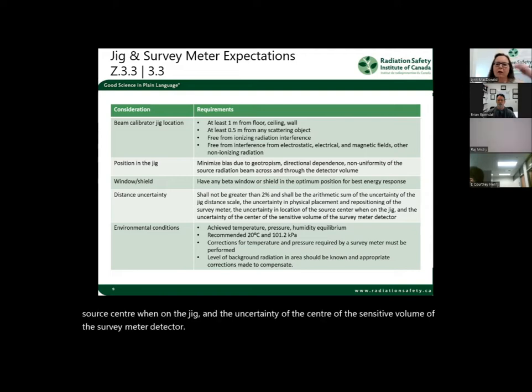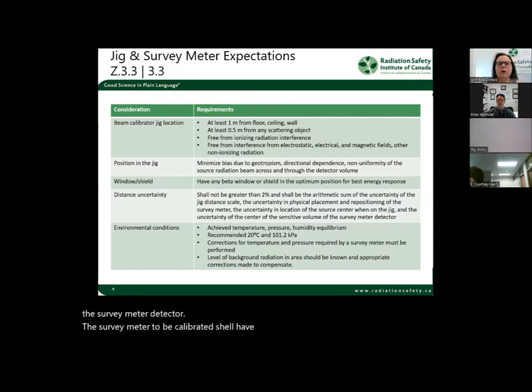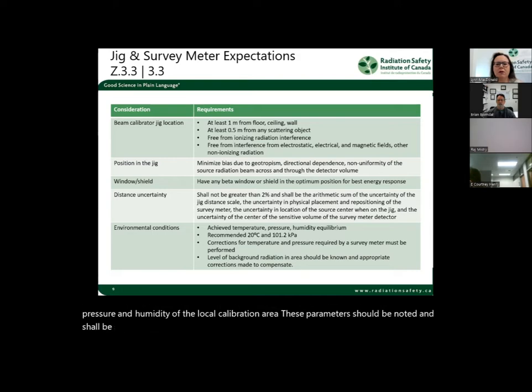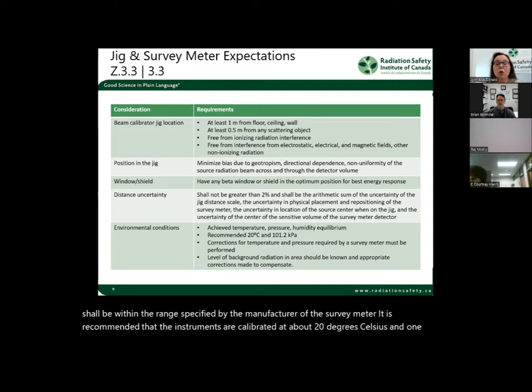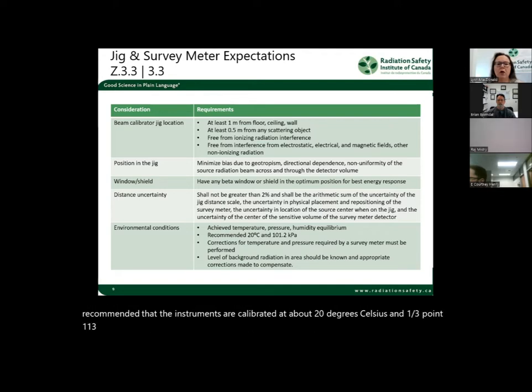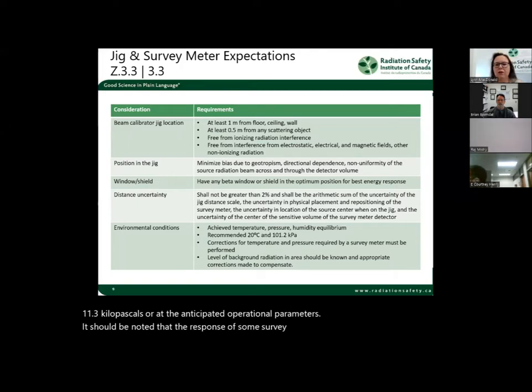The survey meter to be calibrated shall have achieved equilibrium with the temperature, pressure, and humidity of the local calibration area. These parameters should be noted and shall be within the range specified by the manufacturer of the survey meter. It is recommended that the instruments are calibrated at about 20 degrees Celsius and 101.3 kilopascals, or at the anticipated operational parameters. It should be noted that the response of some survey meters must be corrected for temperature and pressure. Therefore, where required, such corrections must be performed.